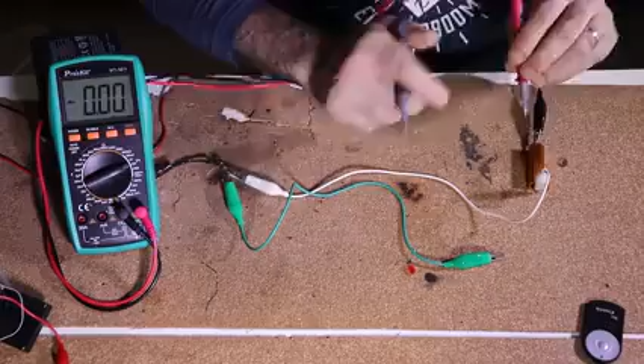then there will be voltage drop across these wires because of their resistance, and the positive line drops by around 2 volts and the negative line rises by around 2 volts. So now if we measure between our earth and neutral, we don't read 0 anymore but around 2 volts. And we can take this voltage and turn something on with it, like this LED.